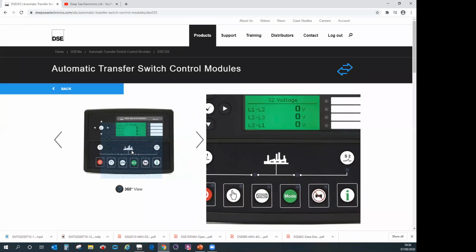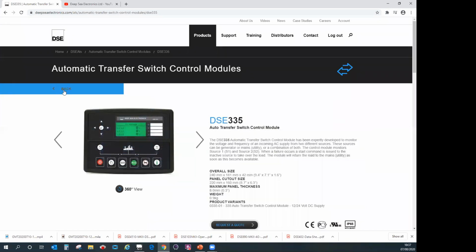So it might be the case that for a large building or a large application, you've got what's called a transfer room where all the opening and closing of the breakers take place. And then in another room, remote from the ATS room, you might have all the generators. So you'd have what we call a generator house. You might have three or four generators in there, and that's where all the generator controllers are. So that's why you would have an ATS in one room and then a genset controller in the other room.